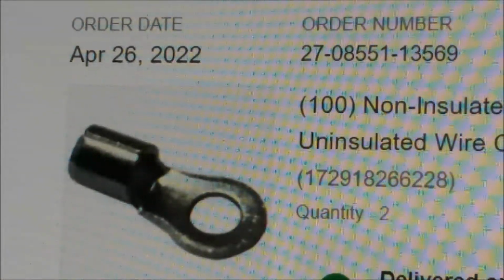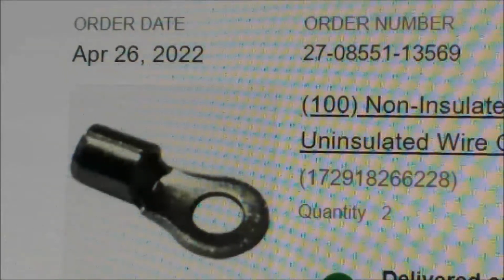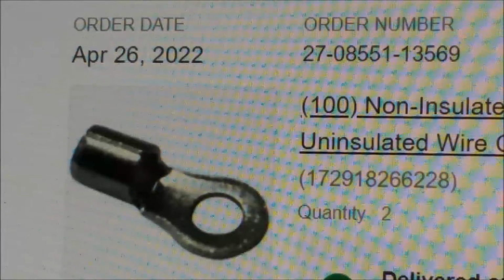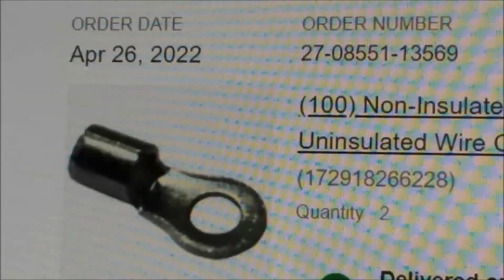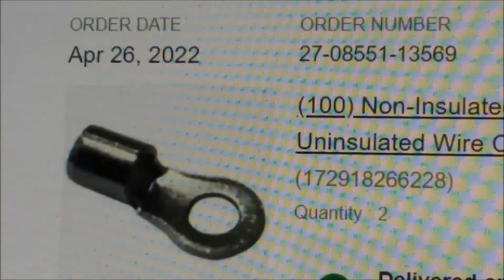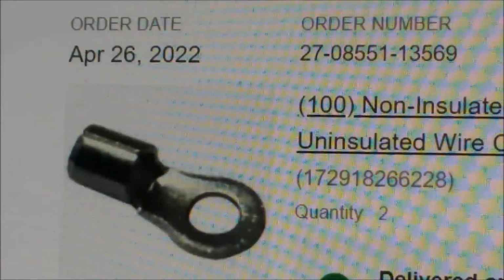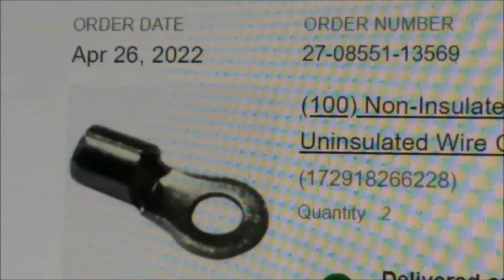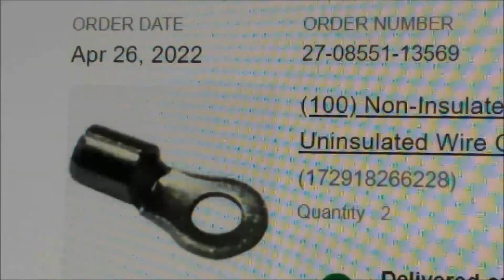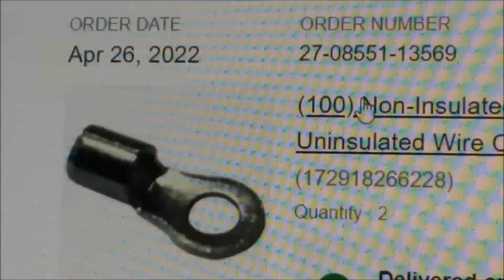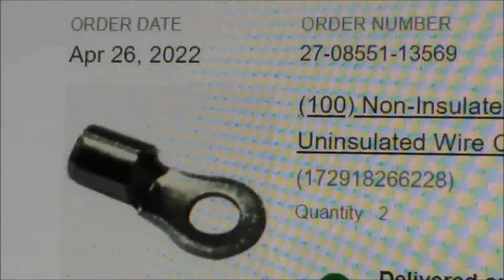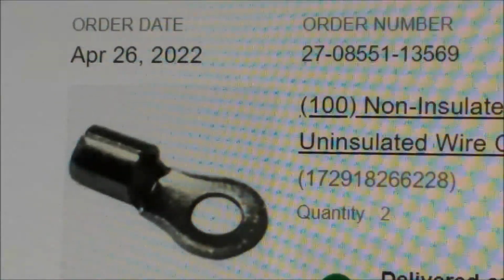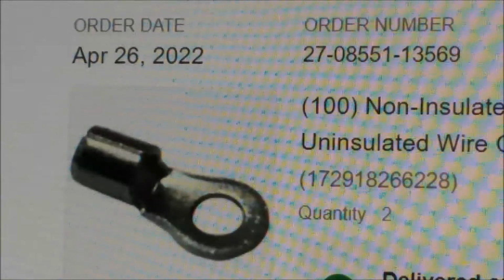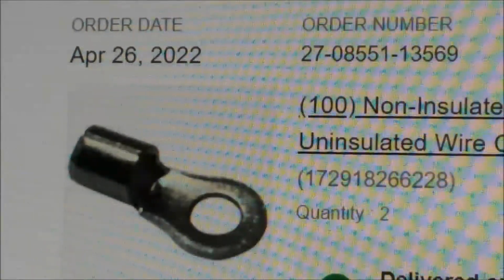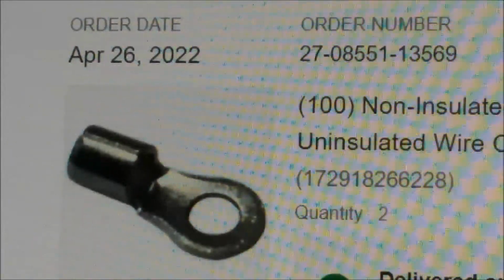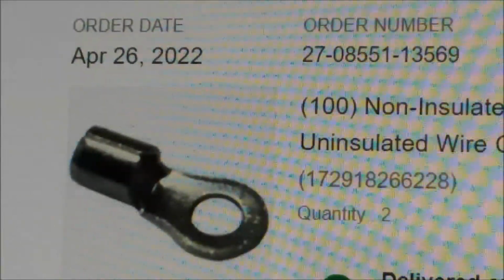We're going to use 12 gauge wire. We could have gotten these in 1412 or 1210, but I've got some other uses I want for this. So we added more for the BMSs—there are 17 of them per battery, and we've got 6 of those big batteries, so this is going to use up pretty much this bunch. These go to something else we'll show you in a little while. It's a specialty terminal block, because the BMS connects a lead to all these, and then you have a balancer. We're going to use active balancers, so that's another 17 wires connected.